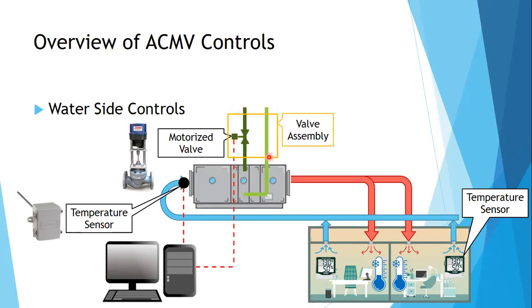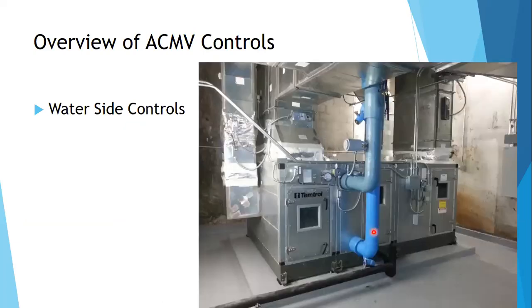But this motorized valve will need a valve assembly. So this valve is not alone. It has other brothers, sisters, cousins to help it so that the water here can be effectively controlled. What are included in this valve assembly? For example, this is your air handling unit. This is the valve assembly right over here. This is your control valve. So this is your valve assembly right here.